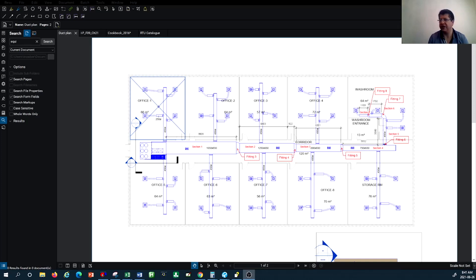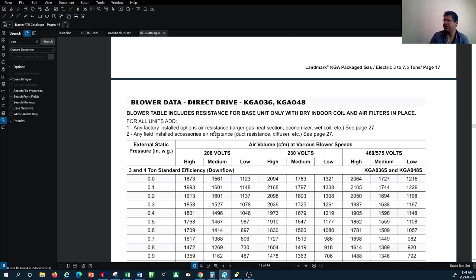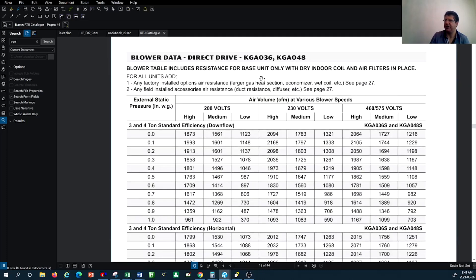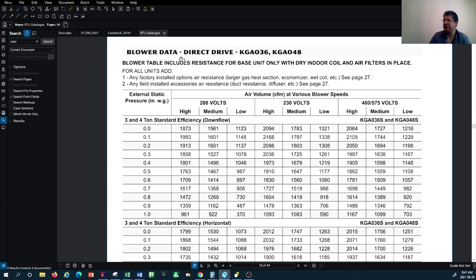I'm going to show you very quickly a catalog from one of the rooftop units. I downloaded this from Lennox, which is a manufacturer of rooftop units — here is the blower data, which is the actual fan information. For their 3 to 4 ton unit, on the left-hand side this column shows the external static pressure that this fan motor can overcome.